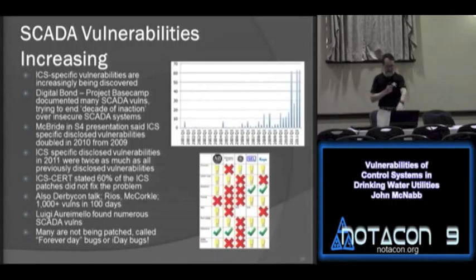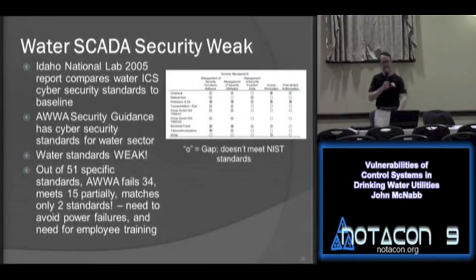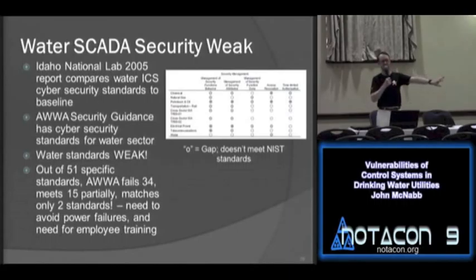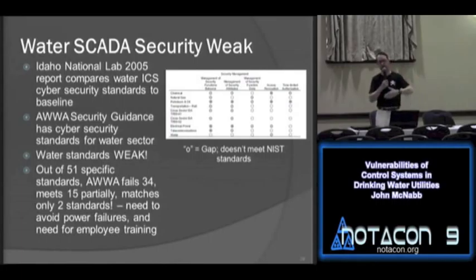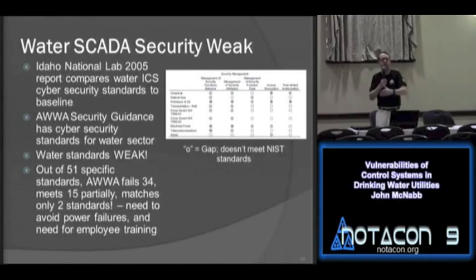Water SCADA security is weak. The Idaho National Laboratories in 2005 compared many industries to a baseline standard for control system security. Out of 51 standards, American Water Works standards for the water industry failed 34, partially met 15, and matched only two — the need to avoid power failures and the need for employee training. Everything else they're not meeting. But that's not even the most important thing, because no one's enforcing the standards — the AWWA standards are voluntary.